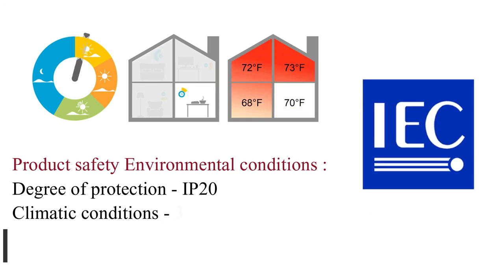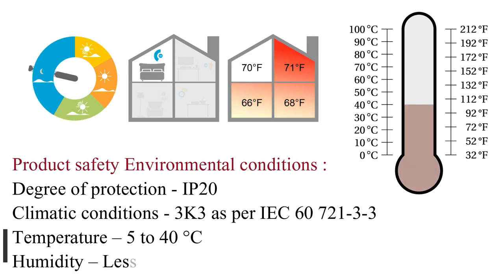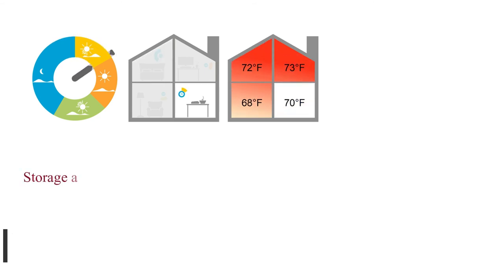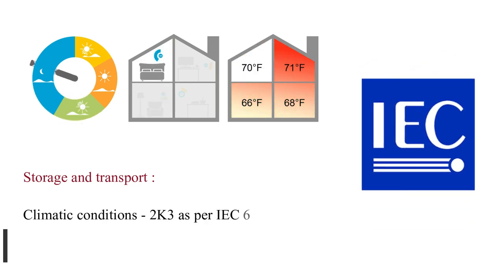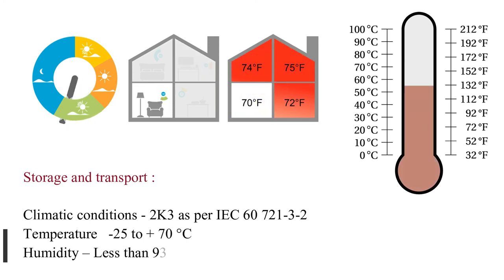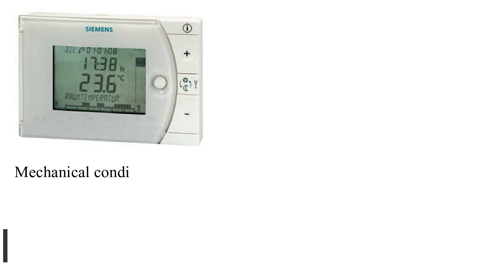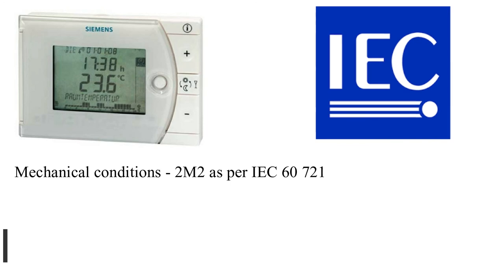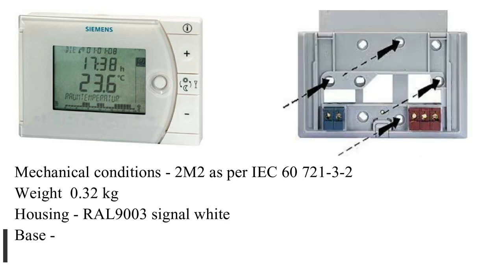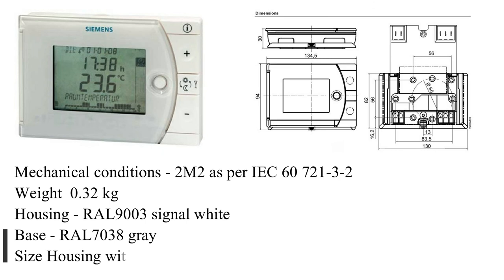Actual value display: 0.2°C. Time display: 1 minute. Product safety — environmental conditions: degree of protection IP20. Climatic conditions 3K3 as per IEC 60721-3-3, temperature 5 to 40°C, humidity less than 85% RH. Storage and transport climatic conditions 2K3 as per IEC 60721-3-2, temperature −25 to +70°C, humidity less than 93% RH. Mechanical conditions 2M2 per IEC 60721-3-2. Weight: 0.32 kg.